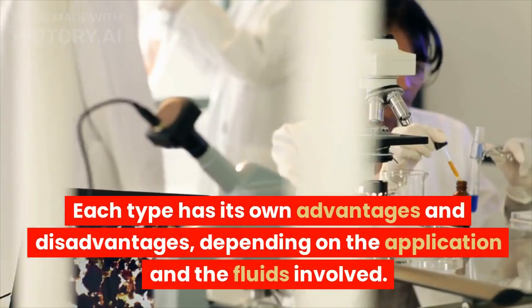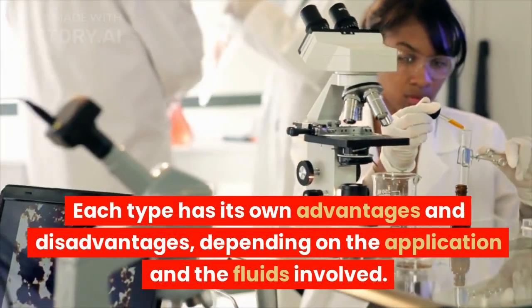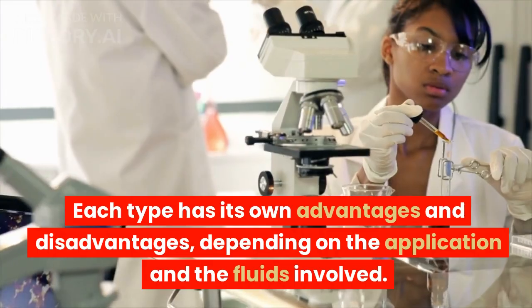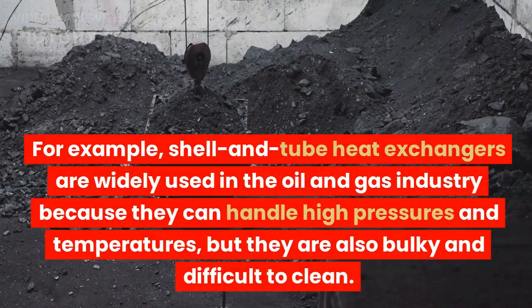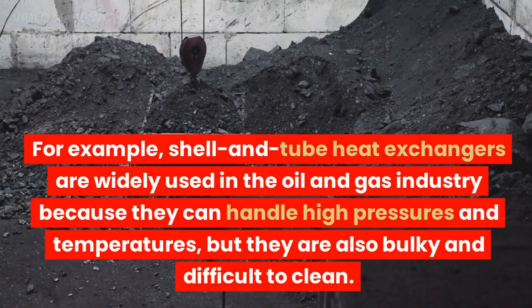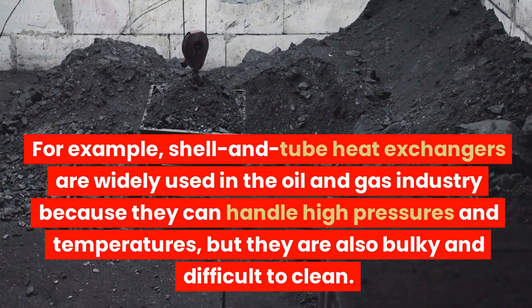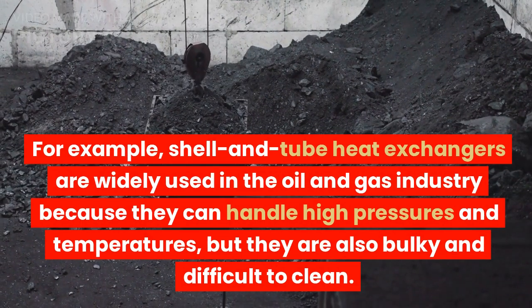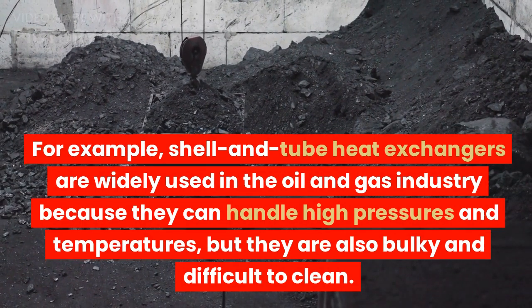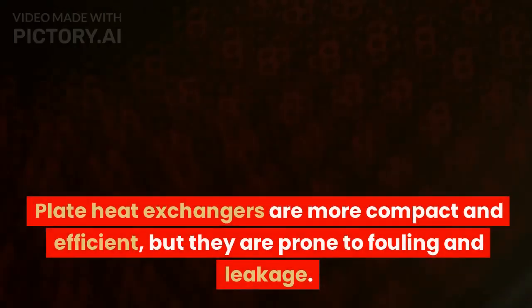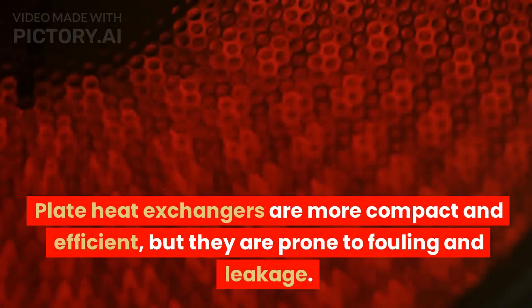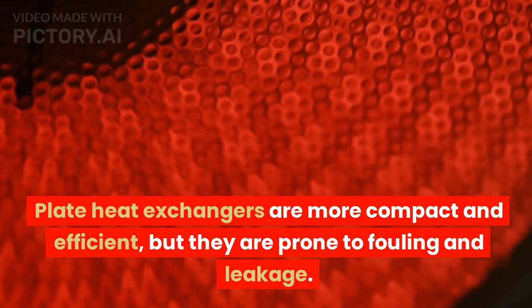Each type has its own advantages and disadvantages, depending on the application and the fluids involved. For example, shell and tube heat exchangers are widely used in the oil and gas industry because they can handle high pressures and temperatures, but they are also bulky and difficult to clean. Plate heat exchangers are more compact and efficient, but they are prone to fouling and leakage.